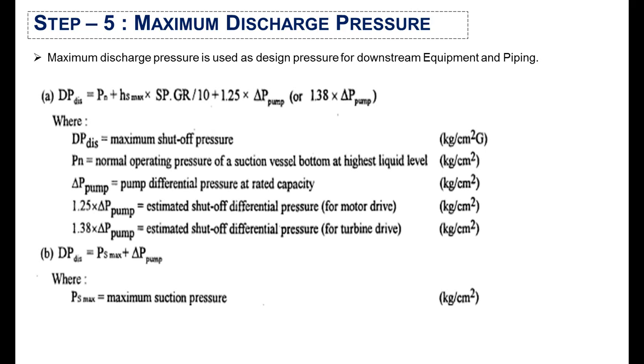In the fifth step, we will calculate the maximum discharge pressure. The maximum discharge pressure is the sum of the maximum suction pressure calculated earlier and the pump differential pressure at rated capacity. The pump differential pressure is multiplied by a factor depending on the driving force: 1.25 for motor-driven pumps and 1.38 for turbine-driven pumps. The maximum discharge pressure is important for designing downstream equipment and piping.